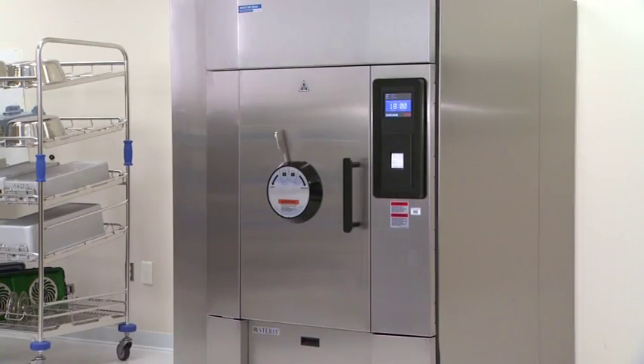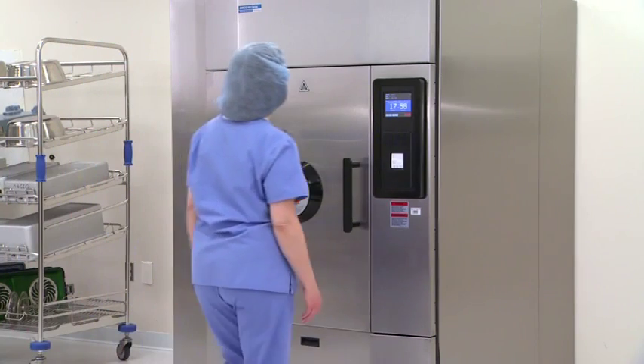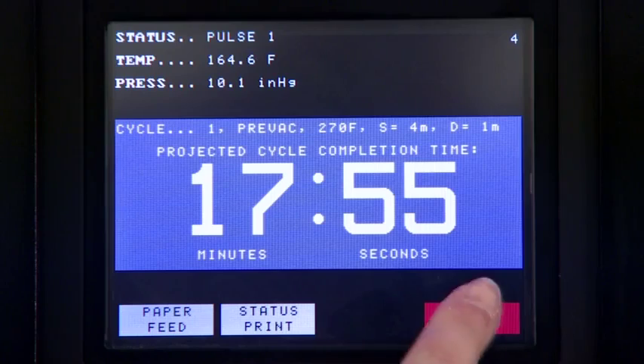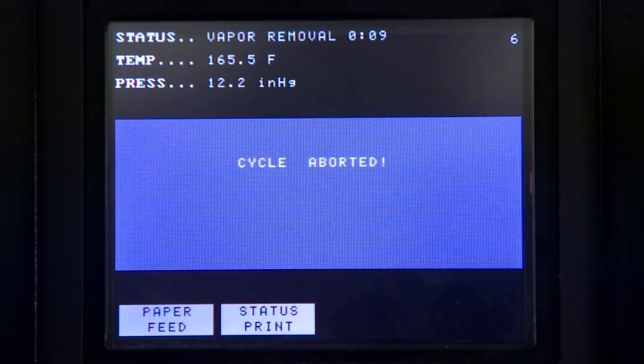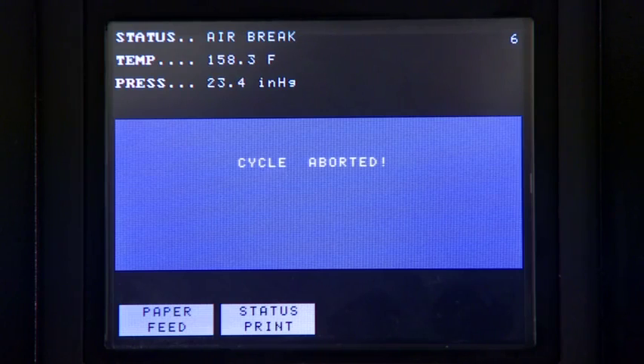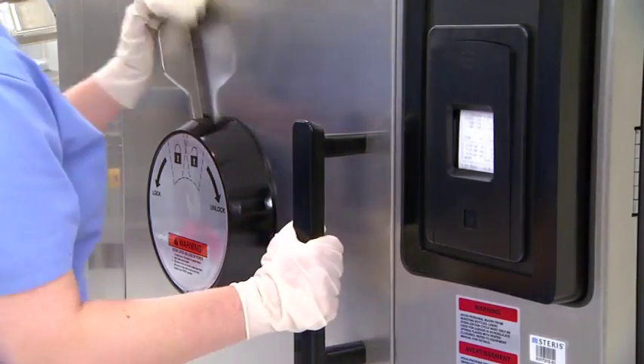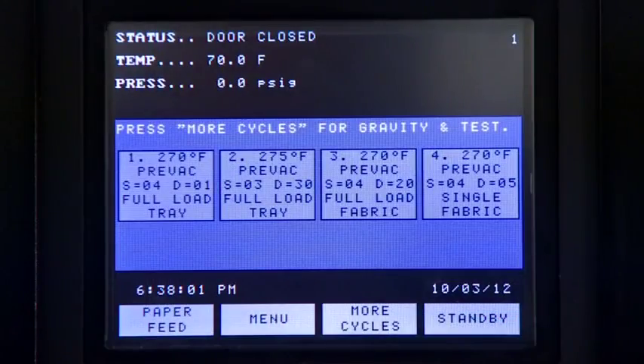At times, there may be an occasion to end a cycle before it finishes normally. For this, you use the Abort touchscreen pad. A cycle only needs to be aborted if an abnormal condition or a control problem develops during the cycle. Pressing Abort causes the sterilizer chamber to decompress if pressurized or air break if in vacuum. The door seal deactivates, the control prompts the operator to open the door, and the sterilizer returns to its normal out-of-cycle state. If an abnormal condition persists after fully aborting the cycle, contact your supervisor or a qualified service technician before trying to operate the sterilizer further.